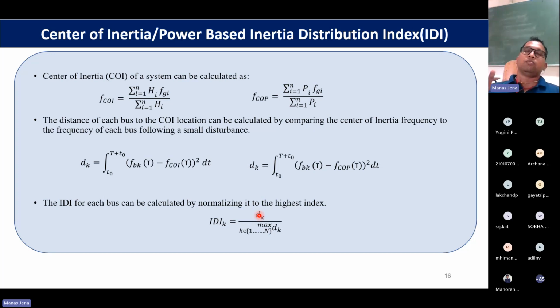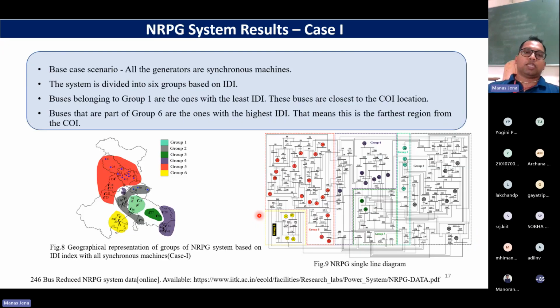So all the buses will have their inertia distribution calculated between 0 to 1, and we tried to apply this to the northern regional power grid. It's, I think, a 246 bus system having 60 generators, and this is the single line diagram of the system, a very complicated system actually. What we did, we tried with the base case. Base case means all 60 machines are conventional synchronous machine based. With the base case, we saw how the inertia distribution is.